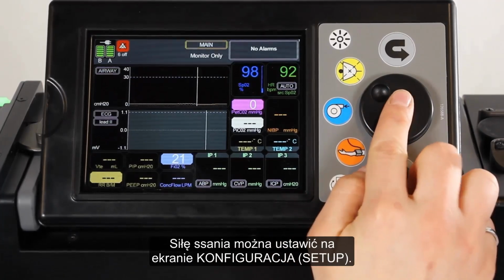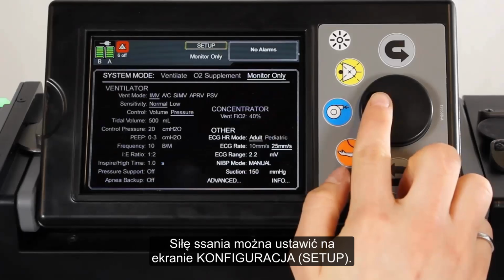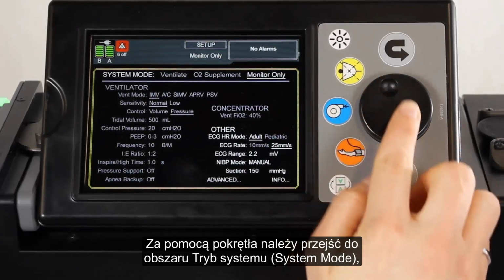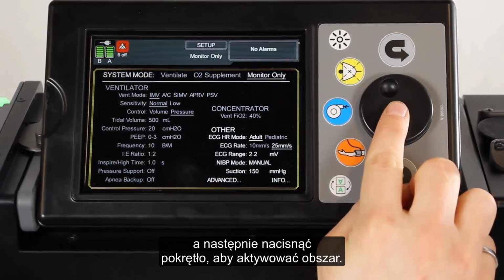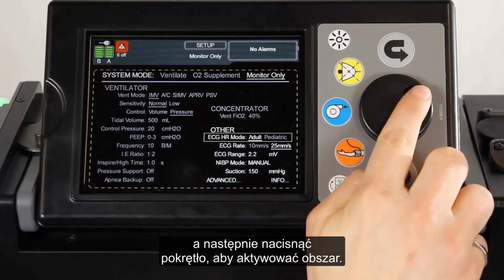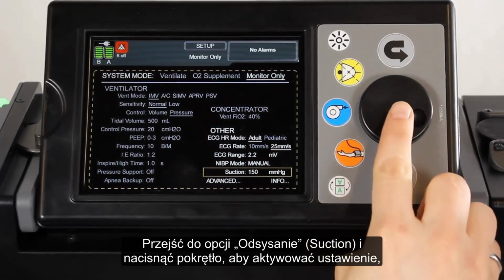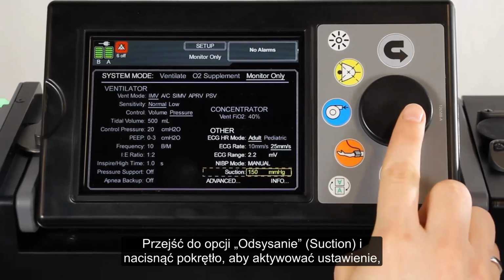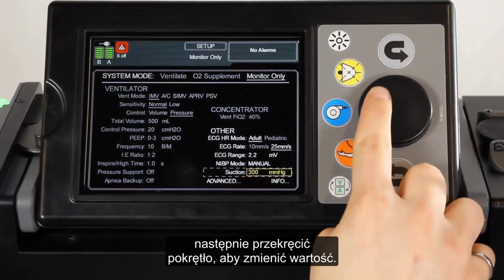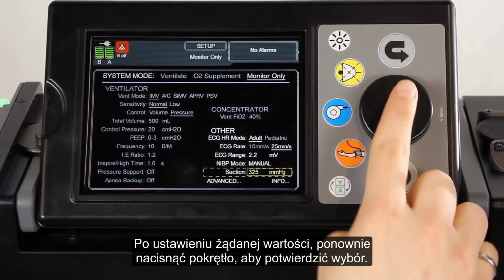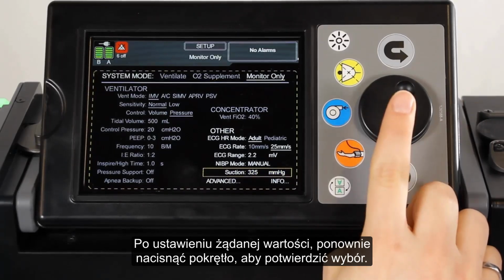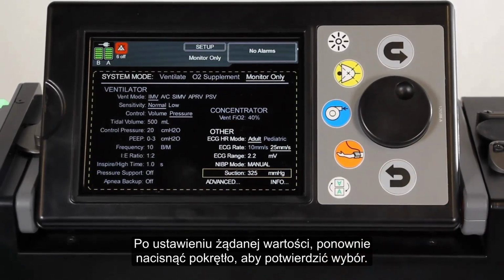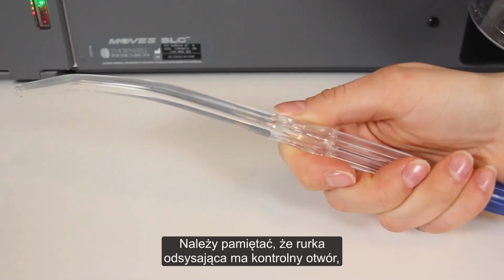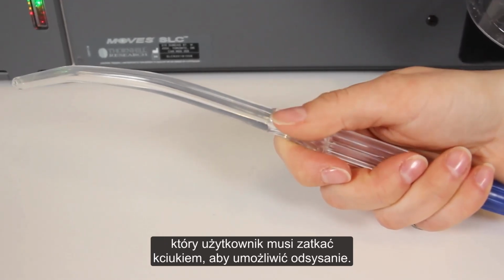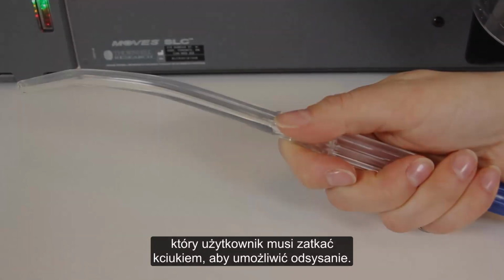To set the suction level, navigate to the setup screen, use the jog wheel to navigate to the system mode area, then press the wheel to activate the area. Navigate to suction and press the jog wheel to activate the setting, then scroll to change the value. Once the desired value is reached, press the jog wheel again to confirm. Note that the suction wand has a control vent that must be occluded by the operator's thumb to allow suction to occur.